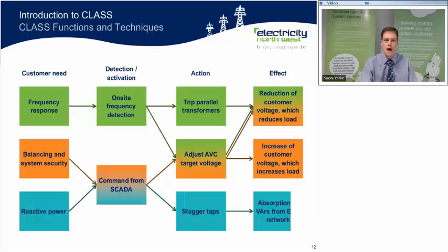And then the final function is the provision of reactive power, or the provision of a reactive load, to assist in the management of voltage at higher voltages. And again, this is activated using a command from SCADA. The action is that we will stagger taps, which I'll describe shortly, which will absorb VARs from the EHV network and so help to reduce the voltage as part of the voltage management of higher voltage networks.